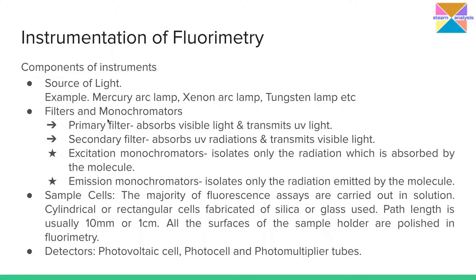Similarly, in spectrofluorimeters, we have monochromators as wavelength selectors. We have two different monochromators: the excitation monochromator and the emission monochromator, both used within a single instrument. The excitation monochromator isolates only the radiation absorbed by the molecule, and the emission monochromator isolates only the radiation emitted by the molecule. These two make up one monochromatic system in spectrofluorimeters, whereas primary and secondary filters make up the wavelength selector system in fluorometers.